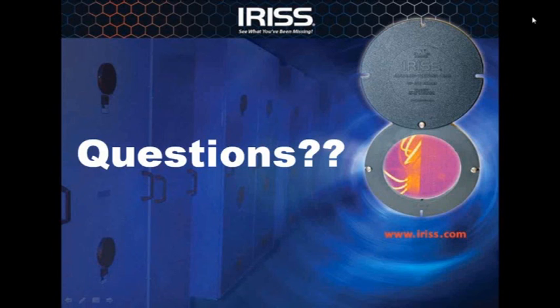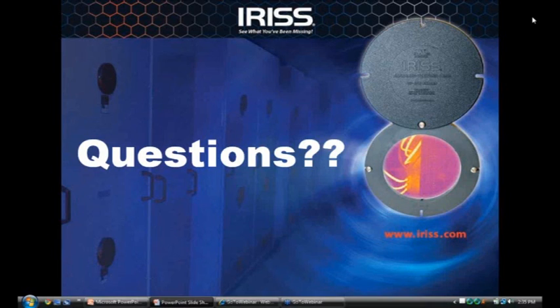So an ultrasound port is a port with a hole size no larger than 1/2 inch or IP2X. That's the largest hole size we can have in a piece of switchgear. That has no membrane or lens or anything in it. It's a straight through vent, so I can put the ultrasound equipment up against there, measure, and close. Now, don't forget, 95% of electrical equipment is not sealed. You do not need ultrasound ports for those. We can go through door seams, we can go through ventilation grills, we can use contact probes.